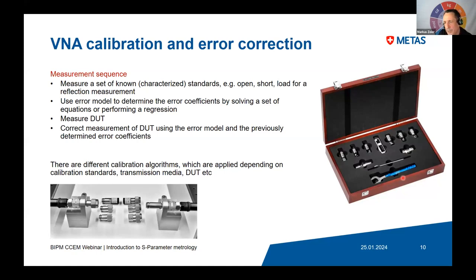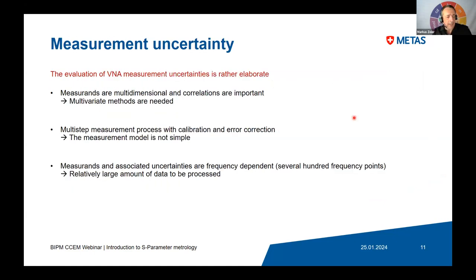You can see here on the right side a photograph of a typical calibration kit, containing open, short, loads for male interfaces and female interfaces. Then there are also different calibration algorithms which can be applied. I'm not going into details here, but it depends on which calibration standards you're using, what type of transmission media you have, and what type of DUT you have. But time is too short to get into detail here. So these were basically the basics of how VNA measurements are done.